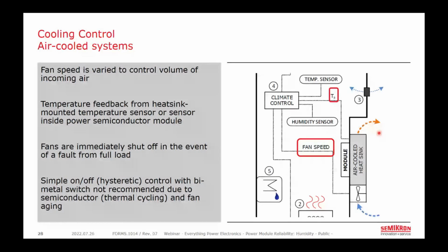And if we monitor the outside air temperature, we can also make sure that we're not drawing in very cold air, such that the heat sink itself is not cooled below the dew point for this condition, where we can risk condensation. Of course, there are other considerations here, such as ensuring that you're not wearing the fan out, as in the case of simple on-off or bang-bang control with a thermostat. As well as controlling the speed of that control loop, so that you don't overheat the semiconductors because the fan is too slow to respond to a change in speed that you've given to it. Nevertheless, this fan speed control approach is something that many companies have already implemented for purposes of system efficiency or even audible noise. So that may be something that's already available to the system.